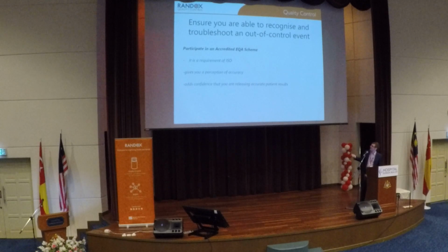So also, we should participate in an accredited EQA scheme. EQA is one of the best ways of detecting particularly calibration errors in your lab. If you have a calibration error, quite a deep-seated one, generally that is not picked up by your day-to-day QC.